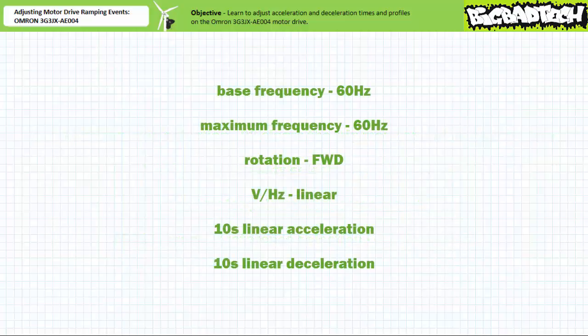This start state establishes a 60 Hz base frequency, a 60 Hz maximum frequency, forward default rotation, a linear volts per hertz ratio, a 10 second linear acceleration time, and a 10 second linear deceleration time among other properties. This motor drive is now ready for today's activities.